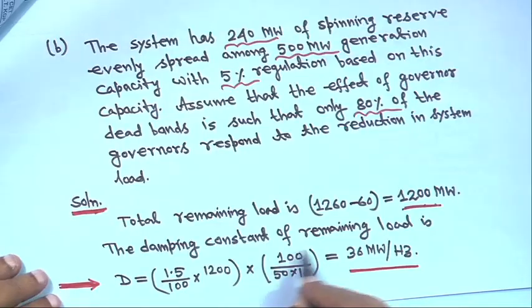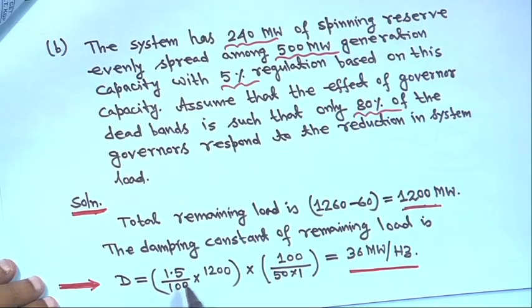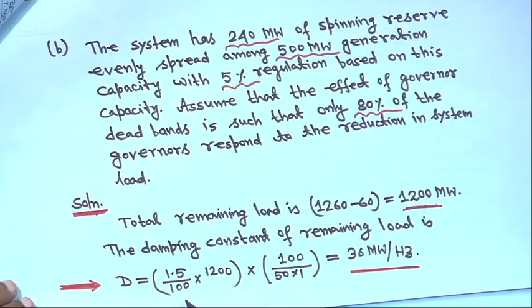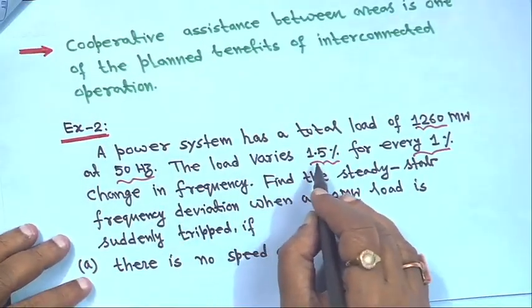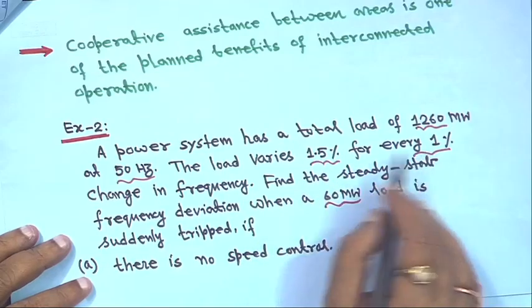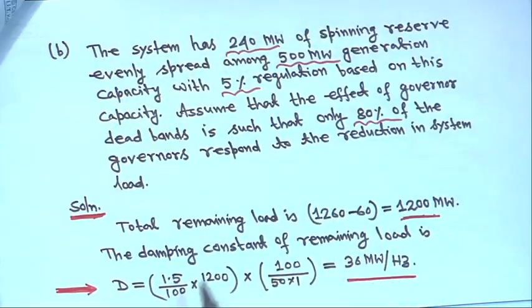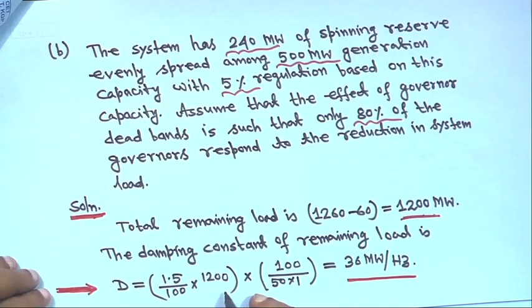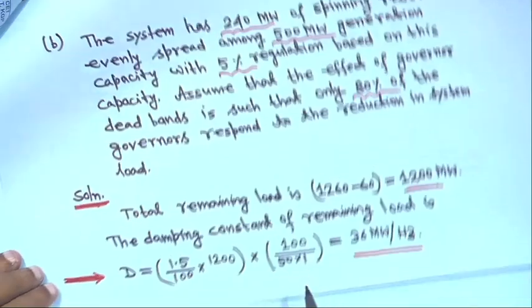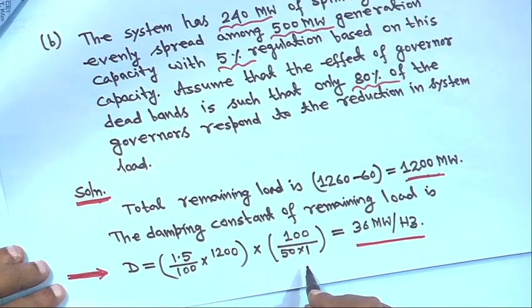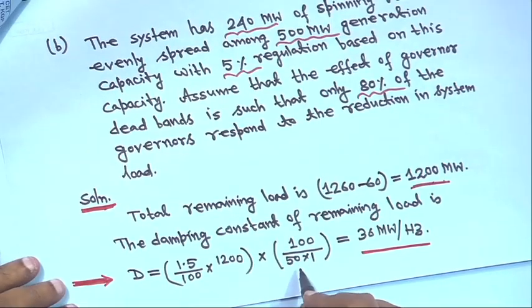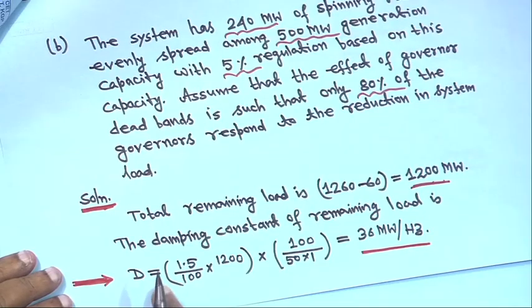So the damping constant of the remaining load is D equal to 1.5 upon 100 into 1200, because it is given that the load varies 1.5% for every 1% change in frequency. So this is 1.5 upon 100 into 1200 into 100 upon 50 into 1. For simplification, I have written everything for you. This is the type of problem we have seen before also. So it is 36 megawatt per hertz.